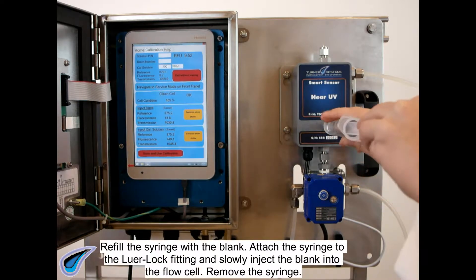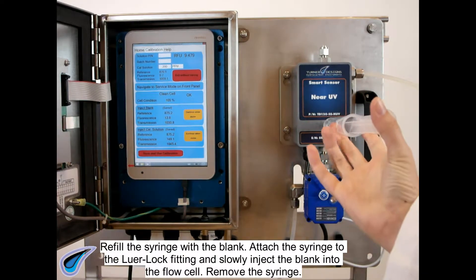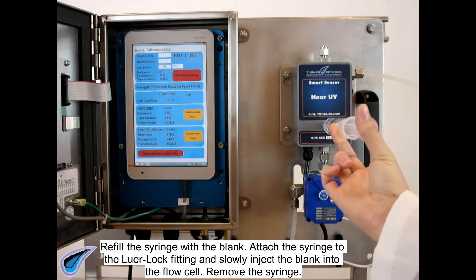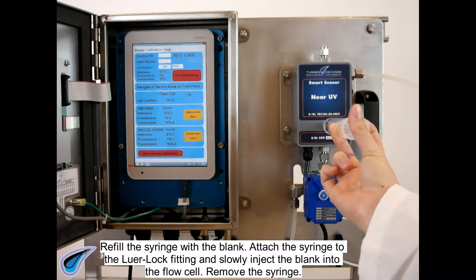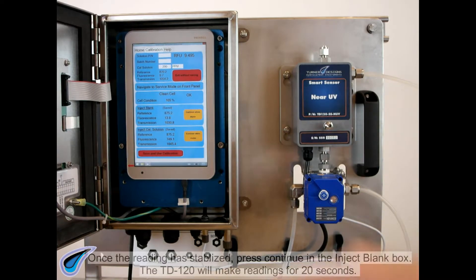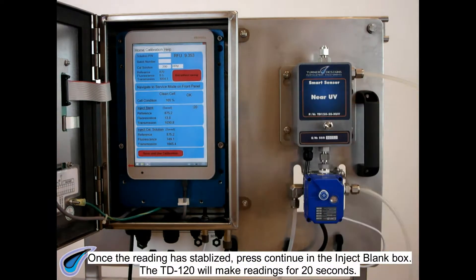Refill the syringe with the blank. Attach the syringe to the Luer-Lock fitting and slowly inject the blank into the flow cell. Remove the syringe. Once the reading has stabilized, press Continue in the Inject Blank box.